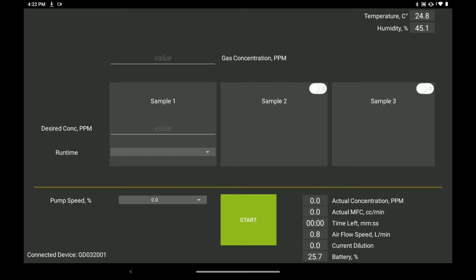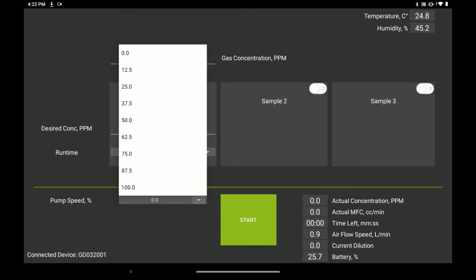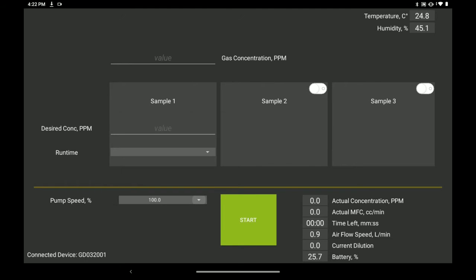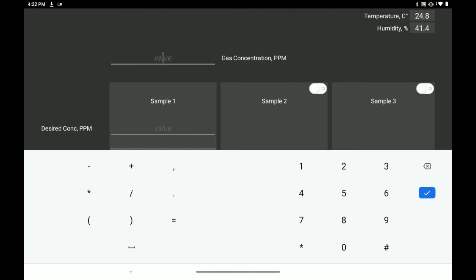So you can then start the pump, and the airflow will be shown here. Now we can put in the value for our gas concentration. This is actually the concentration of the gas cylinder that you have. In our case, we're using a 25 ppm H2S gas canister, so I'd put 25 ppm here.